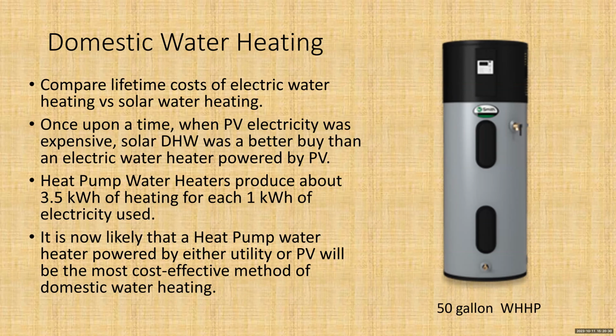It adds somewhere in the neighborhood of 5,000 BTUs per hour to the water, so it takes a little while longer to recover from hot water use. But if you can schedule your water use to give this unit time to recover, it's fine. It also has a backup 4,500 watt element in case you want hot water faster. That's why it's called a hybrid water heater — you can give it full power if you need to heat water faster.